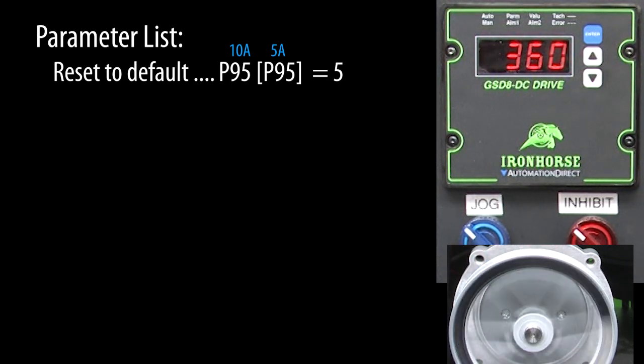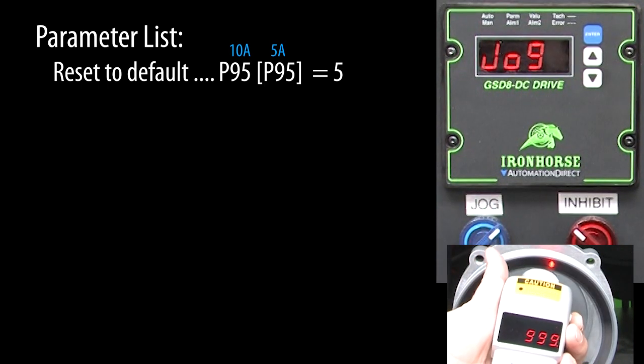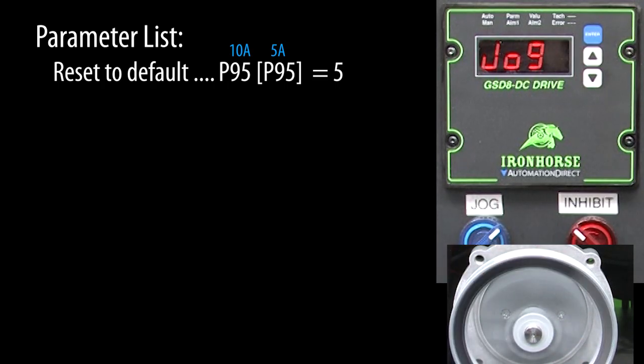The jog speed defaults to 1000. So if we enable jog, sure enough the motor goes immediately to 1000 RPM. Note that it does that immediately, it doesn't wait for the acceleration or deceleration times. I'll release the jog and it resumes the speed we had before.